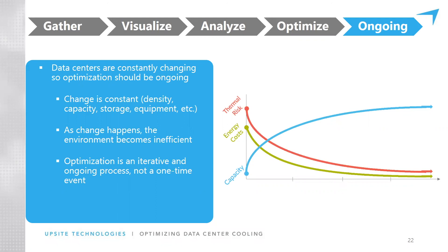The math turns out that cooling represents somewhere around 73% of the non-IT load. So if you take away what's going to the IT equipment and ask how much of the remaining power goes to cooling, it's about 73%. That makes cooling a huge point of leverage in optimizing these facilities.